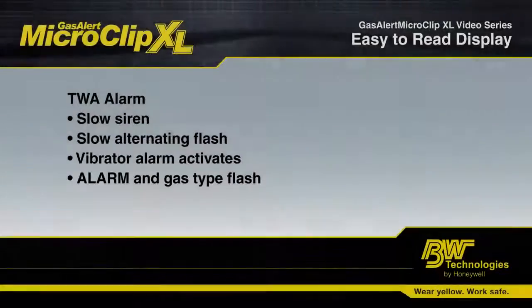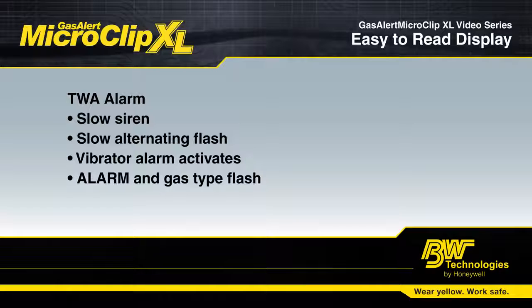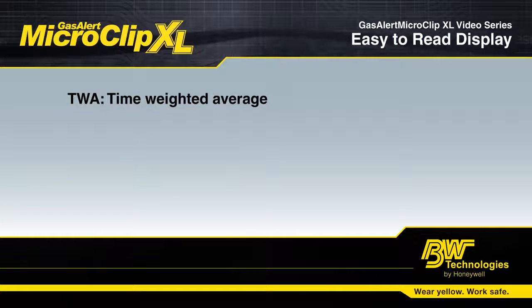Like STEL, TWA alarms are also calculated for toxic gases. A TWA alarm signals a cumulative exposure over time, typically an 8-hour period. TWA stands for Time Weighted Average.